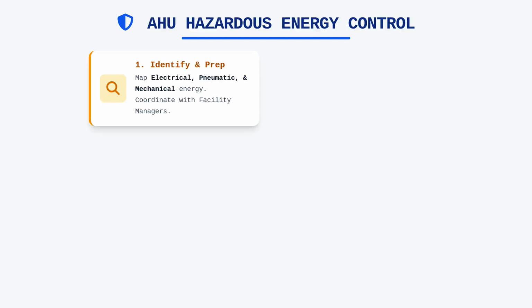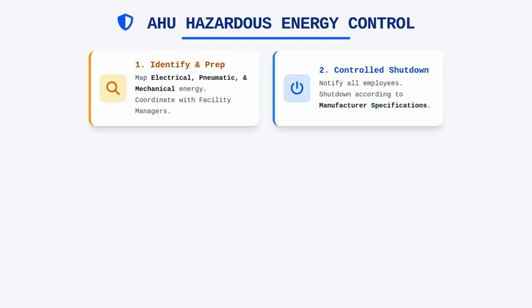The foundation of a successful lockout procedure begins with thorough preparation and clear communication with the building facility manager or the designated site supervisor. You need to notify all affected employees that maintenance is about to occur, followed by a controlled shutdown of the equipment according to the manufacturer's specific instructions.